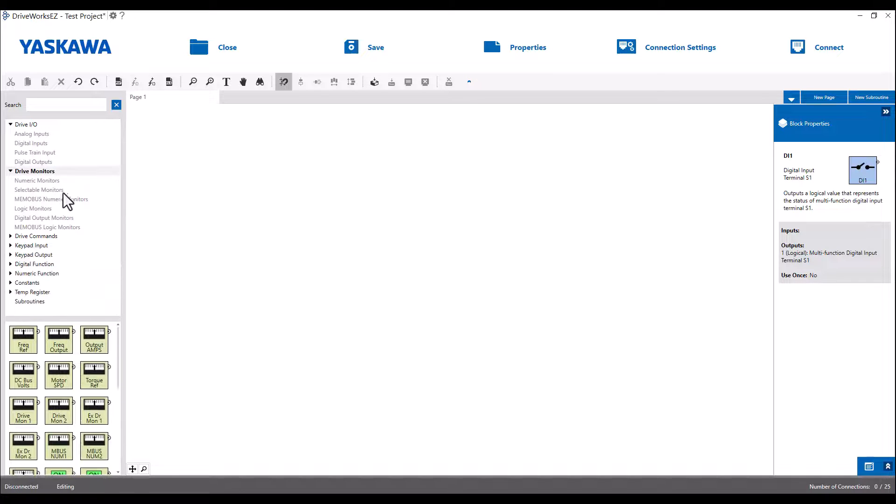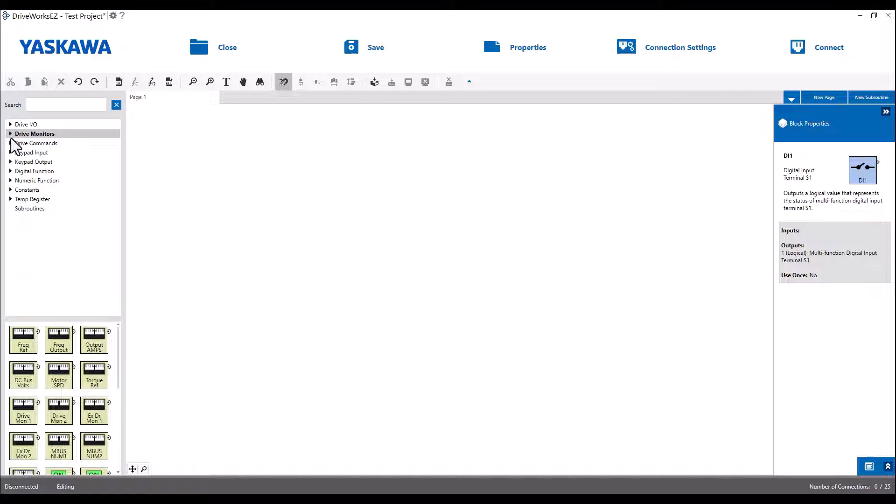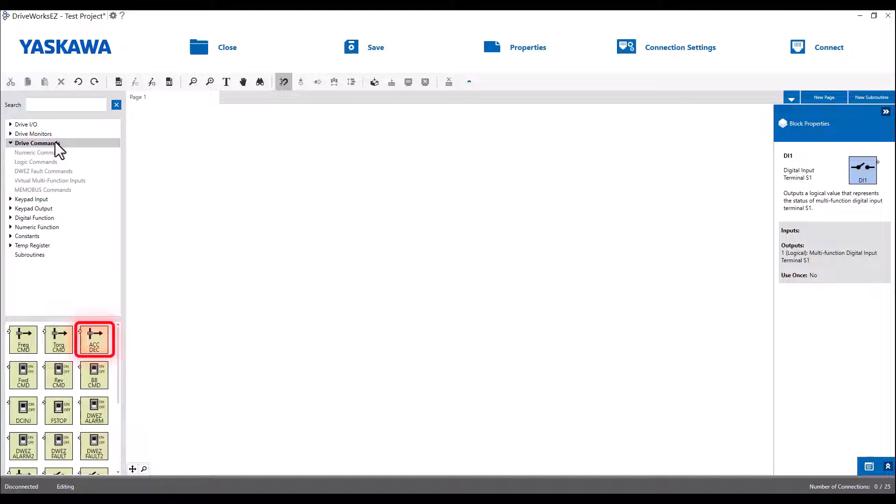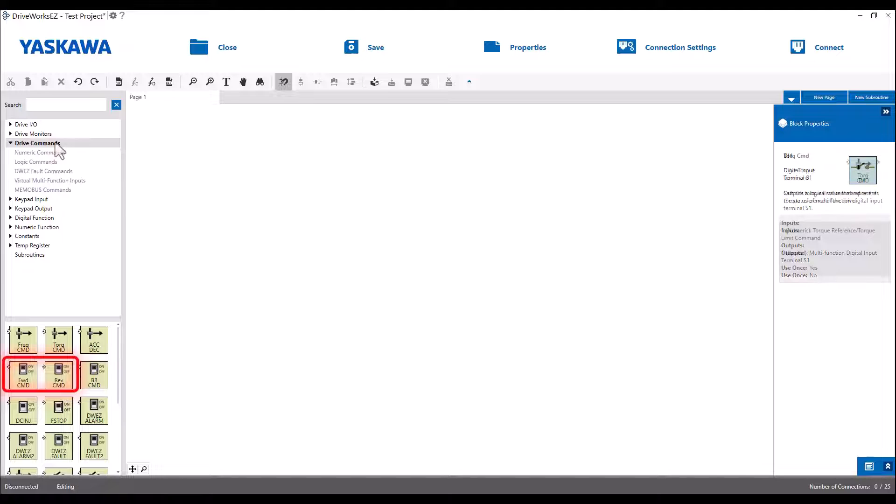The next category is pretty important. Under the Drive Commands tab, you will see some of the most essential drive commands. Frequency command is your frequency reference. Torque command is the drive's torque reference command, and the act dec block can be used to modify your acceleration and deceleration rates. You can also see that we have the forward and reverse run commands available to us here as well.